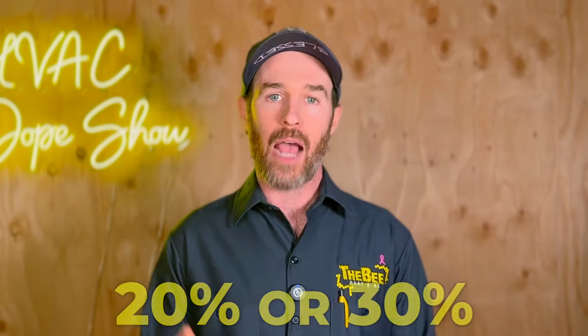Oftentimes the blower wheel can get dirty, and what people don't realize is that something as small as a millimeter of dust on each of the fins can reduce your airflow by 20 or 30%. I've seen a dirty blower wheel reduce airflow enough, especially at higher altitudes, that systems are icing just because they have a dirty blower wheel.